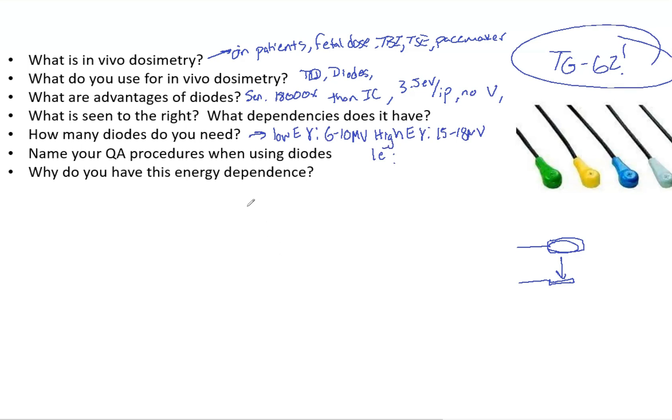So what are the QA procedures with diodes? So this is where you really want to jump into TG-62. They discuss QA, what your expectations should be. So you need to do monthly QA, just like you do on everything else.